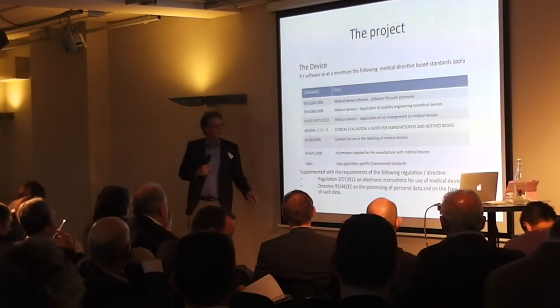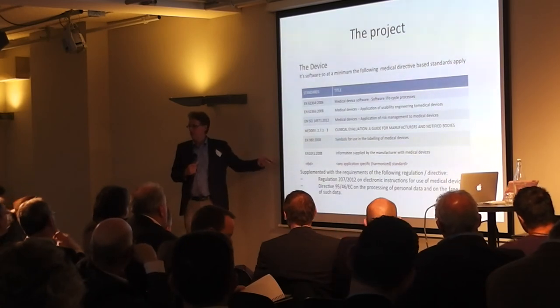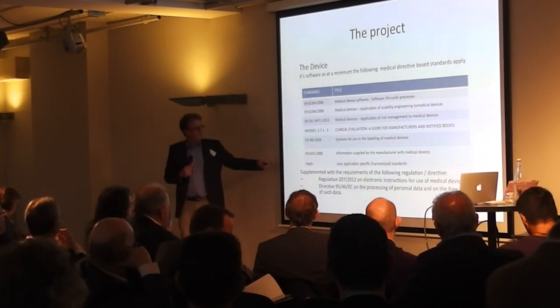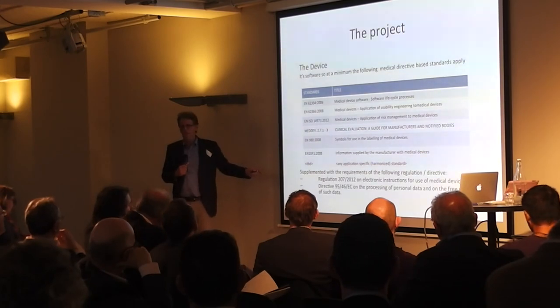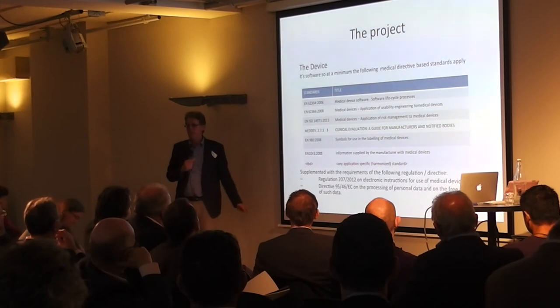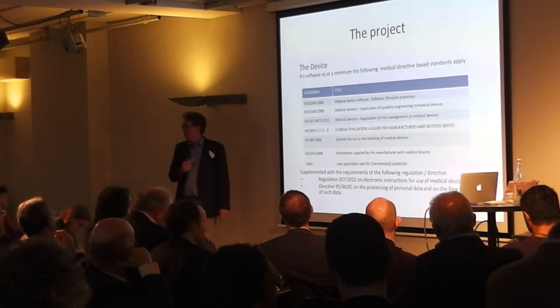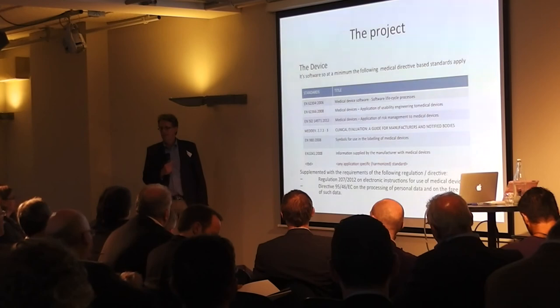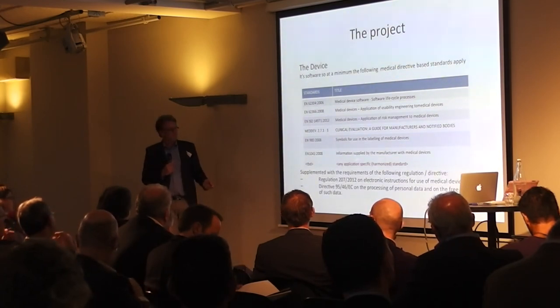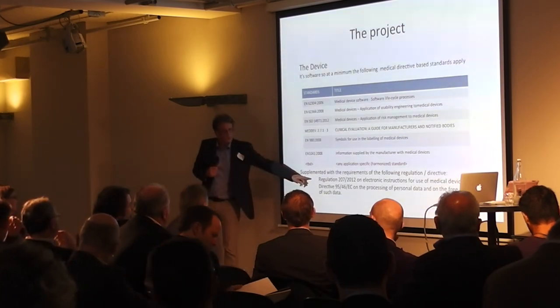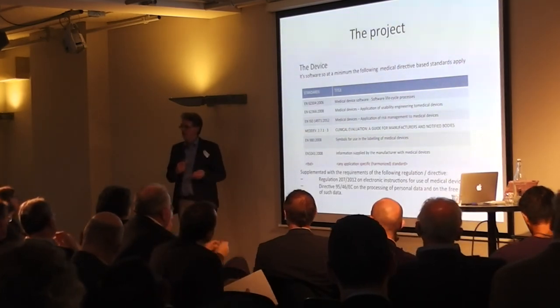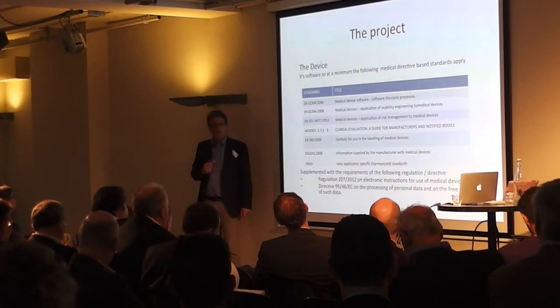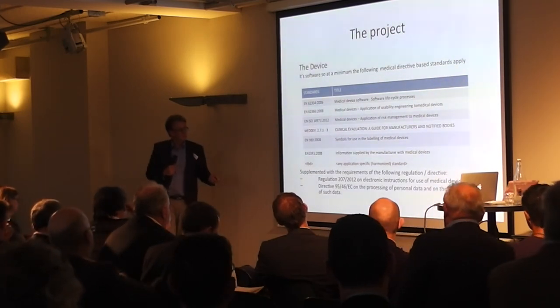And here, the clinical evidence: your product has a clinical functionality, and how can you guarantee that clinical functionality is met? There is a guidance document — a medical guidance document — that addresses the literature search, what data is available, what clinical studies you need to do. And here come the labeling requirements. Medical devices need some labels on the product, and some information needs to be in the IFU — the instruction for use. Medical devices come with an instruction for use, and how do you get an instruction for use into your app? You can't build in a booklet, so how do you deal with that?